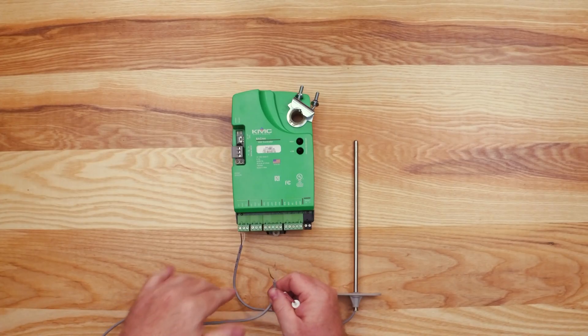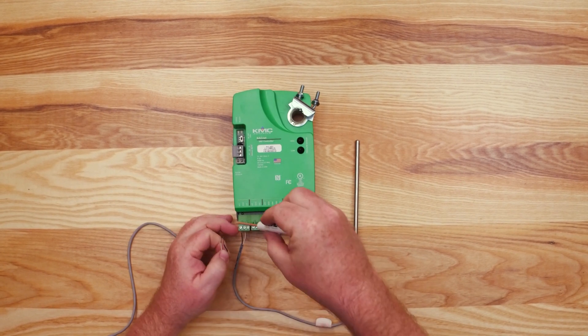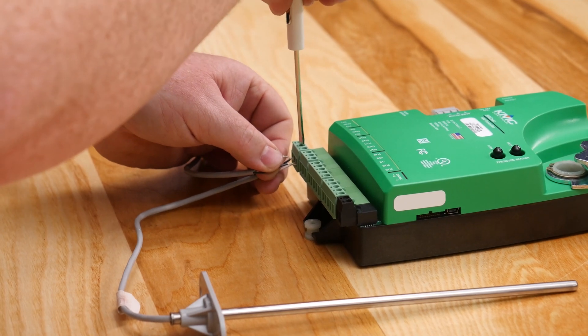The common wires for inputs in the same terminal block can be grounded together in the same terminal. Thus, the common wire for UI4 can go into the same ground terminal as UI3.